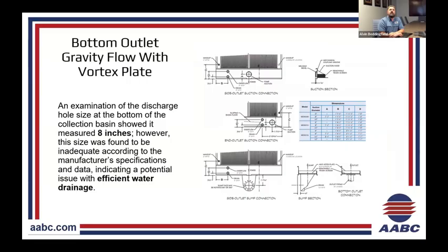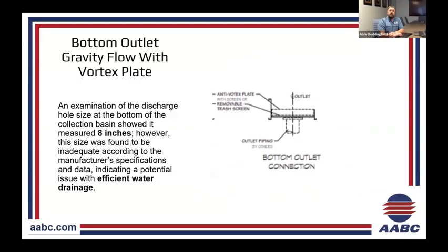After examination of the tower, we had a bottom outlet gravity flow with the vortex plate. That's just the way the tower manufacturer wanted the configuration. When we examined the collection basin, it was a hole at the bottom, an 8-inch round dropped into the concrete basin with a vortex plate, and according to the manufacturer's specifications, this indicated a potential issue with how efficiently we can drain the water out of the tower. So we're going to take away all the other scenarios. The only thing we're looking at right now is the bottom outlet collection. That's the only thing that we have.